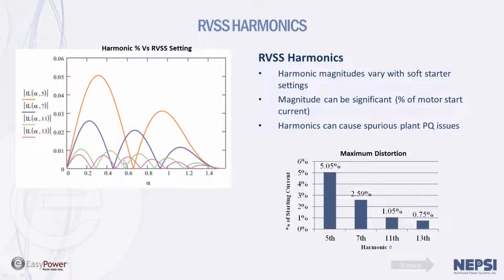We have seen that soft starts have an impact on applications where shunt power capacitor banks are used, as it can sometimes enter into system resonance and cause spurious fuse operation. So whenever applying soft starts in an environment where there are power factor correction capacitor banks, resonance should always be considered in those applications as a possible area of concern.